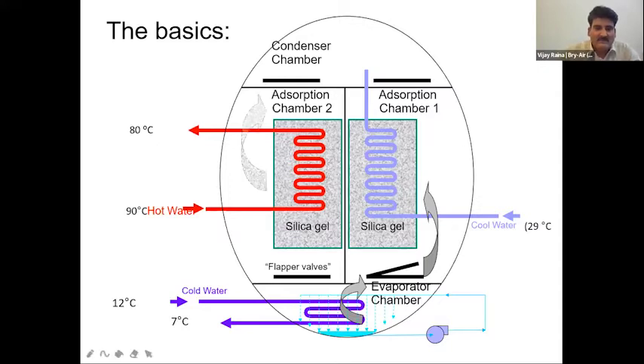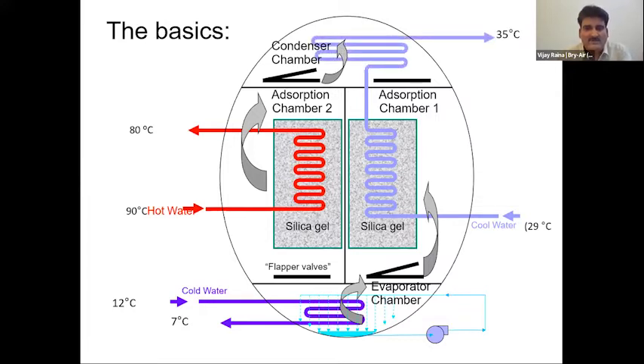evaporator to condenser. Now, when we are giving heat in the adsorption chamber, whatever refrigerant was adsorbed by the silica gel in the 5 minute cycle gets released with the help of hot water. So we call them the cooling and heating chambers: cooling chamber 1 and hot chamber 2. But ultimately, our job is to transfer refrigerant water from the evaporator to the condenser. The same refrigerant is reaching the condenser, and then in the condenser we give cooling tower water. Here, as compared to conventional mechanical chillers, we use more cooling tower heat, because the cooling tower has to move through 2 heat exchangers, the adsorption chamber and the condenser chamber.